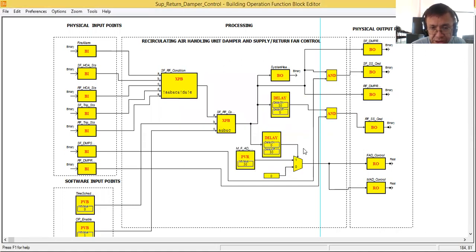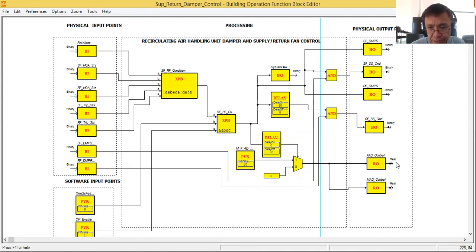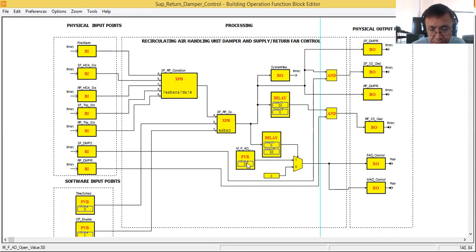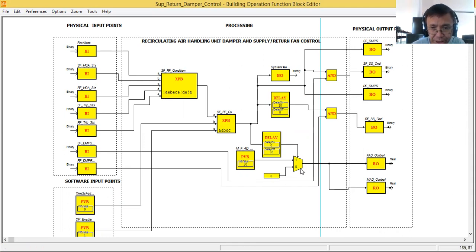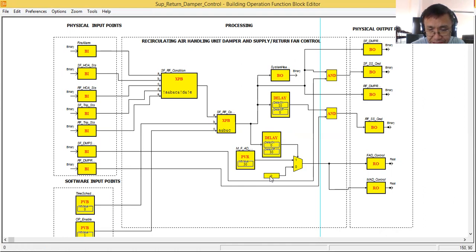Initially I will be giving 50% or halfway open for both the fresh air and mixed air damper. I'm using a digital multiplexer here. This digital multiplexer has two values represented by one and zero. For one, the corresponding value will be 50, given by this parameter value real. For zero, I will give a constant zero. This acts like a switch — if the input coming from this delay is true, it selects the one input giving 50%; if false, it selects zero.